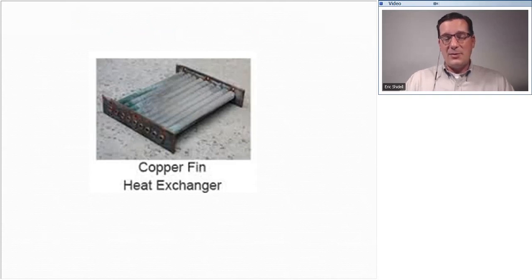Now, this one actually has a problem. Notice that it looks kind of green over here in the corner and kind of white in the rest of the place. This is an example of a boiler operating for extended periods with cool or cold return water temperature. Water temperatures less than 140 degrees are going to lead to flue gases condensing on the boiler heat exchanger surfaces, leaving behind these deposits. Could ultimately even lead to heat exchanger failure. As a result, the passageways between the fins, which are very narrow, begin to get even narrower because of these deposits left behind by that condensation. And that leads to blocked flue passageways, poor draft, sooted heat exchangers, tripped rollouts, things starting on fire, all kinds of bad ideas.